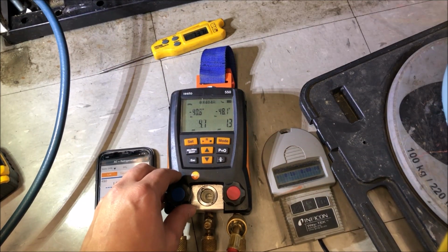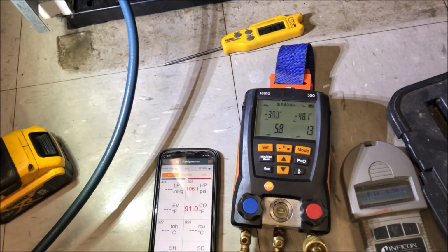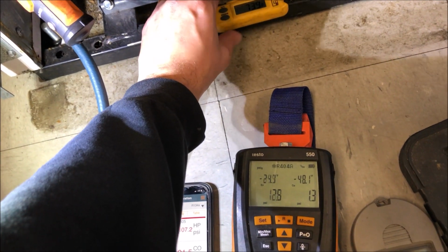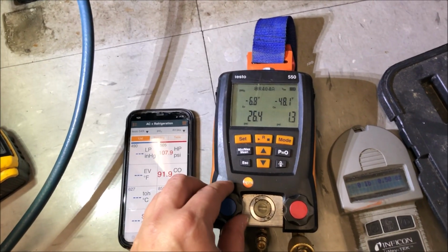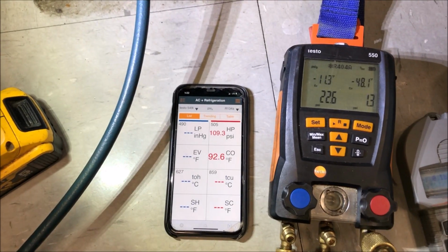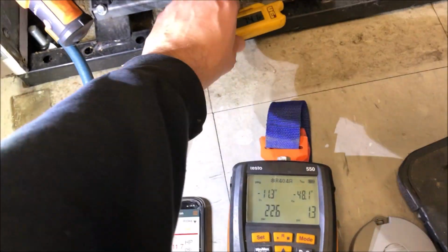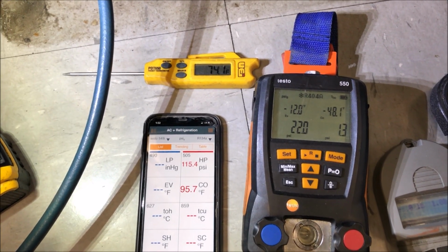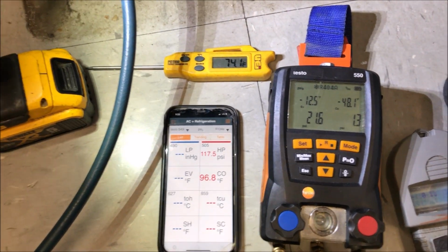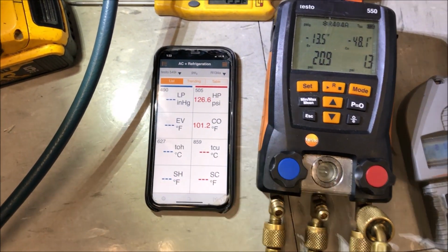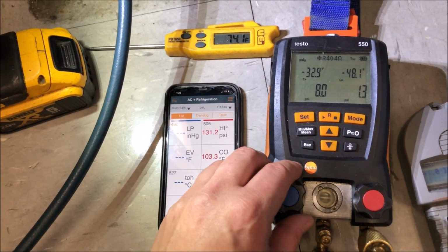Okay, so how I do that is I add in some refrigerant and then we're gonna bring the pressures to pretty close to where they should be. And then based on that, if the pressures are what they should be, it means we were low on charge. If I can't get this thing out of a vacuum or it stays really low on the suction side, that's telling me we have a restriction in the system. All right, so we're just gonna go ahead here and hit the fast forward.